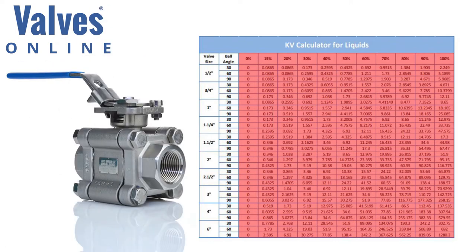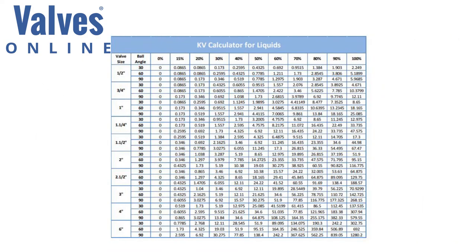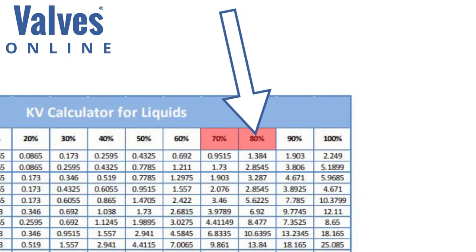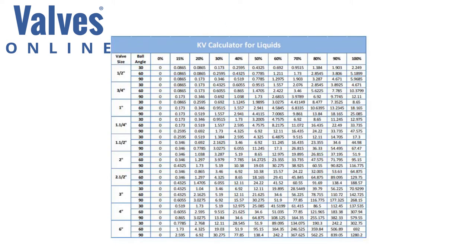To select the flow you require and size up the correct control valve, you'll need to have your flow figure or set point. In selecting the valve, you should aim to look at between 70 to 80 percent open — this will give you between 20 to 30 percent extra flow capacity if needed in future.